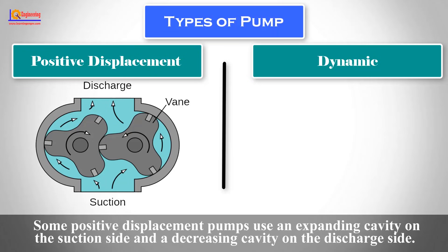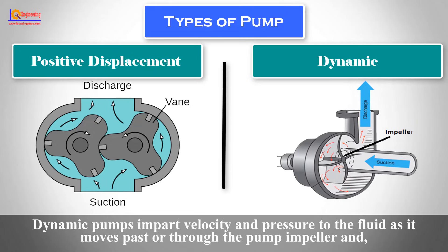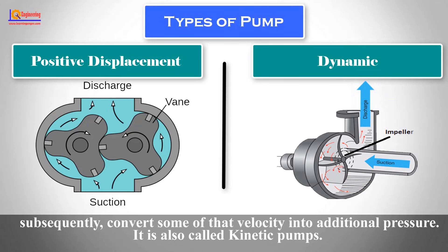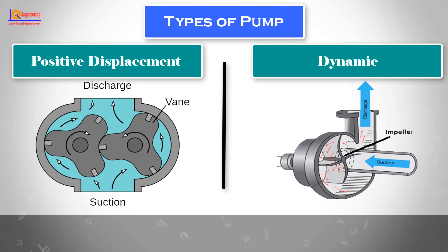Some positive displacement pumps use an expanding cavity on the suction side and a decreasing cavity on the discharge side. Dynamic pumps impart velocity and pressure to the fluid as it moves past or through the pump impeller, and subsequently convert some of that velocity into additional pressure. They are also called kinetic pumps. These pumps operate by developing a high liquid velocity and converting the velocity to pressure in a diffusing flow passage.